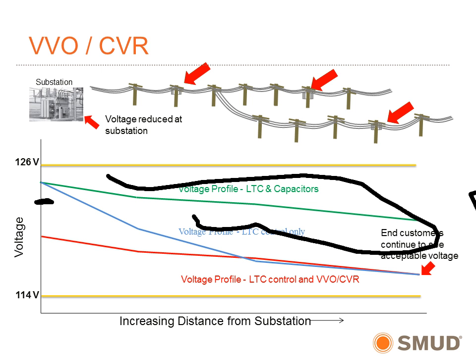We're required to provide voltage between plus 5% or minus 5%. In the US, that's 120 volts, so you have a range of 126 to 114 volts. So basically, this is our bandwidth that we have to work with—we need to provide voltage in that range.